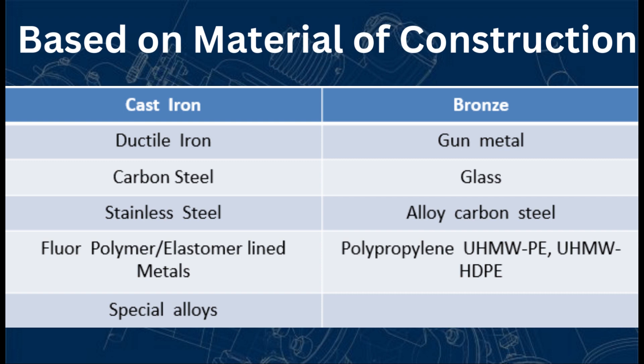The next classification is based on material of construction. A number of combinations are possible, and the piping engineer selects the material in consultation with the process engineer — to suit the process fluid and to suit the environment in which the valve is to be installed. The most commonly available materials are cast iron, ductile iron, carbon steel, stainless steel, fluoropolymer/elastomer-lined metals, special alloys, bronze, gun metal, glass, and alloy carbon steel.